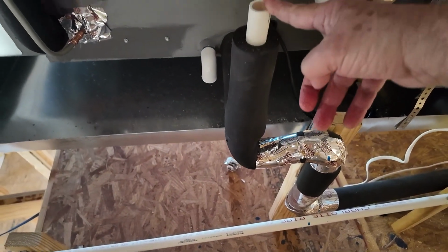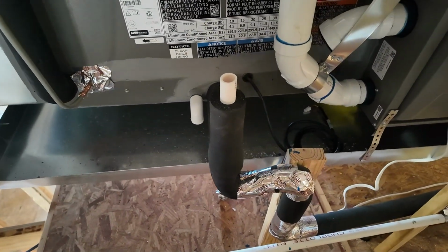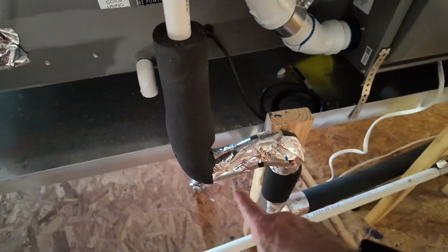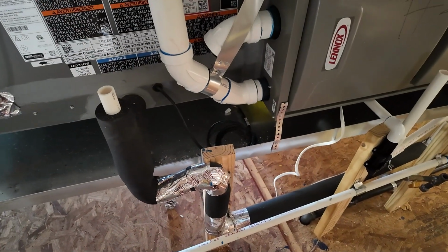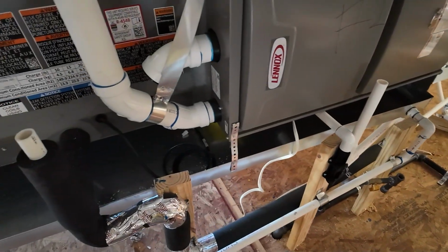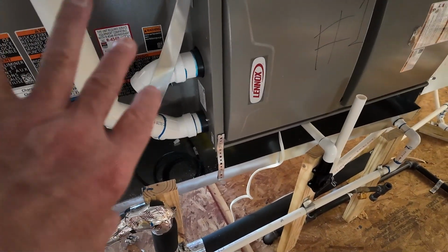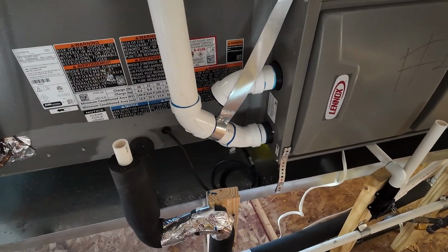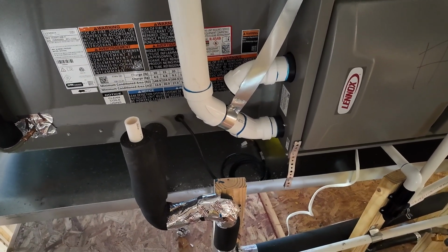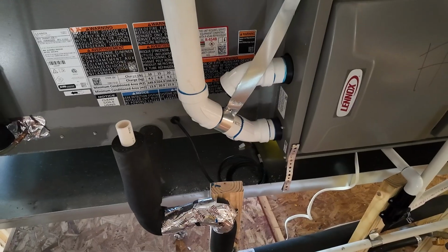When the air conditioner runs, you're going to be air conditioning your attic. Okay, this should have a cap on it, and this pipe should be open, and you shouldn't have a shallow P-trap. Why shouldn't you have a shallow P-trap, bud? Because this is a high-efficiency unit. It's going to run a long time, efficiently. And as it's raking the air through the coils, it simultaneously is going to be dehumidifying the house. What does that mean? It means it's going to extract all the humidity out of the air.